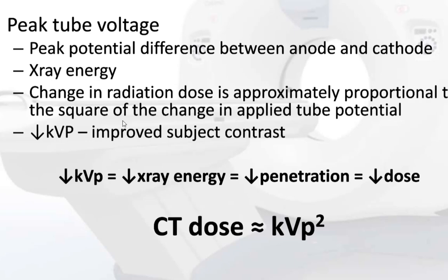KVP is peak tube voltage — the peak potential difference between anode and cathode. It is a measurement of X-ray energy. Change in radiation dose is approximately proportional to the square of the change in applied tube potential. When we decrease KVP, we improve subject contrast, decrease X-ray energy, decrease penetration, and therefore decrease the dose. There is no linear relationship between KVP and CT dose.